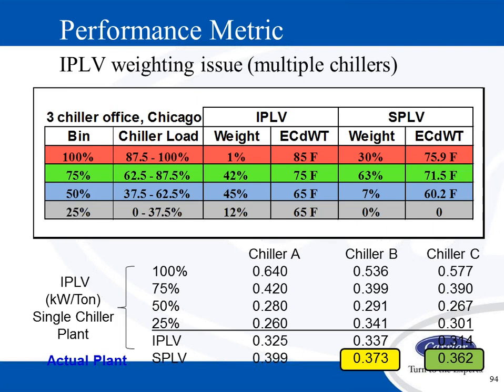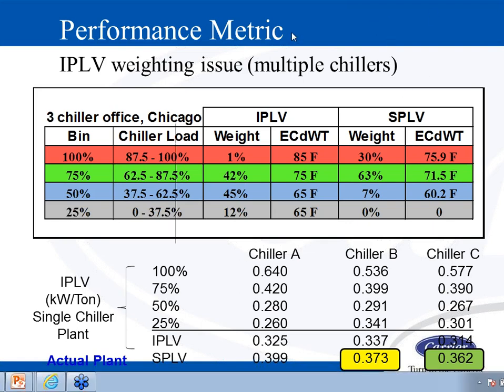Okay, so I want to go on again and look at IPLV and compare another manufacturer who has very good IPLVs, but their IPLV ratings are better at the 50 and 25% load point, and that is typical. Chiller A is a magnetic bearing type machine, and let's look at a multiple chiller plant. Chiller B is our 23XRV, our older compressor, and Chiller C is the 23XRV with a part load optimized compressor. You see at the full load, we look at the IPLV of 0.325 on the Chiller A. Our old Chiller B would be 0.337 part load, and then we have 0.314 part load optimized, comparing that one machine on Chiller C.